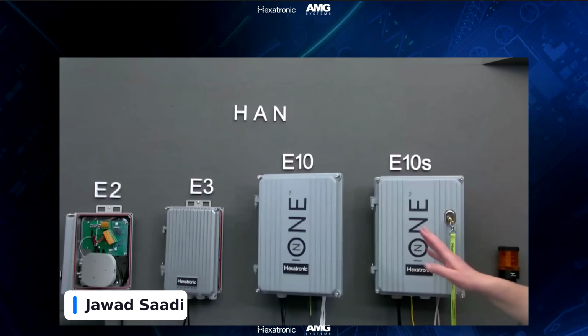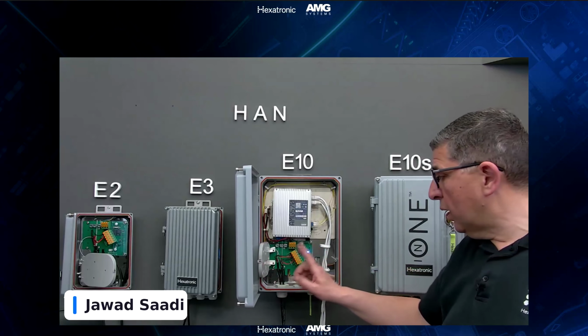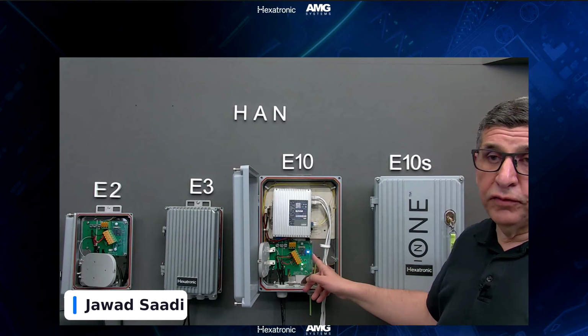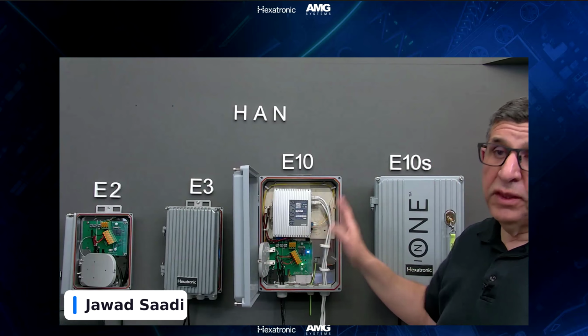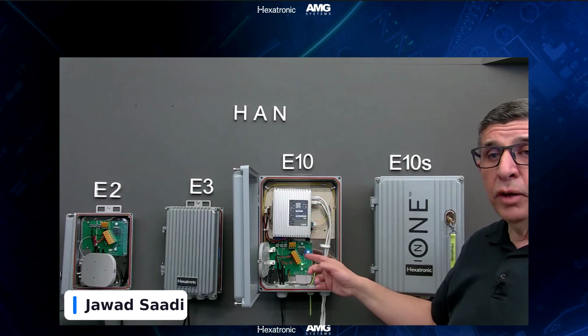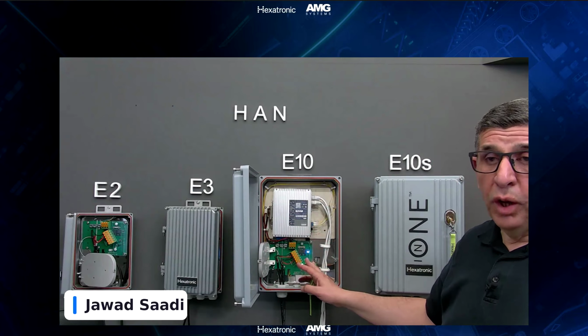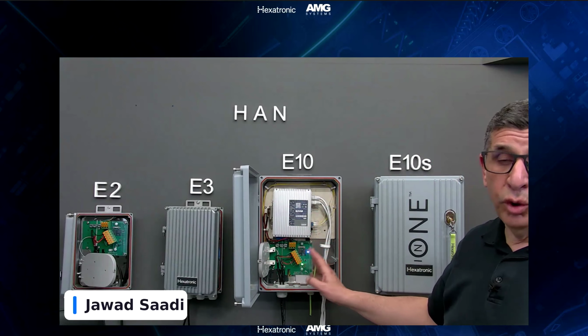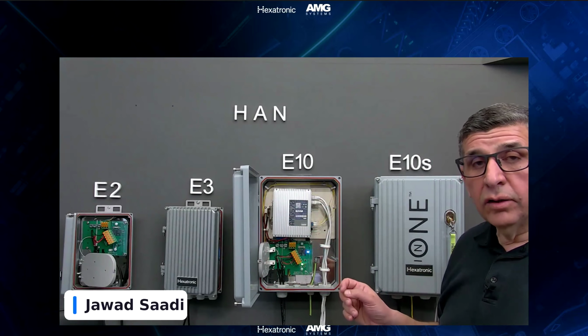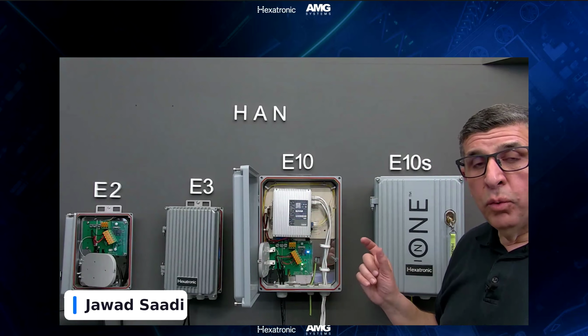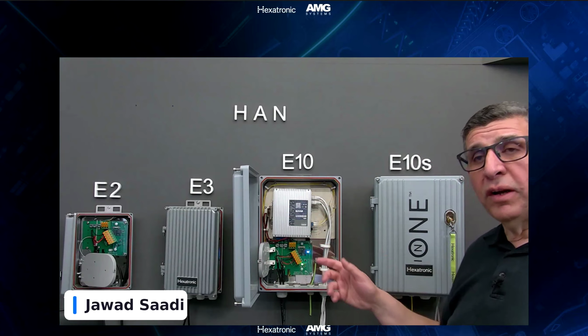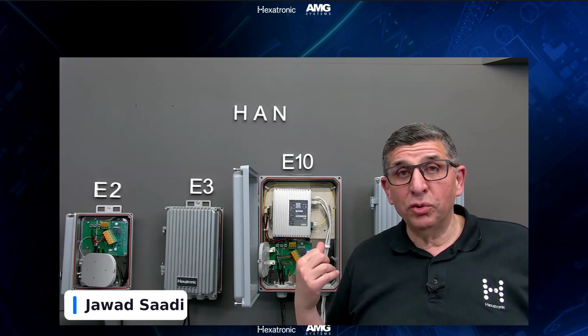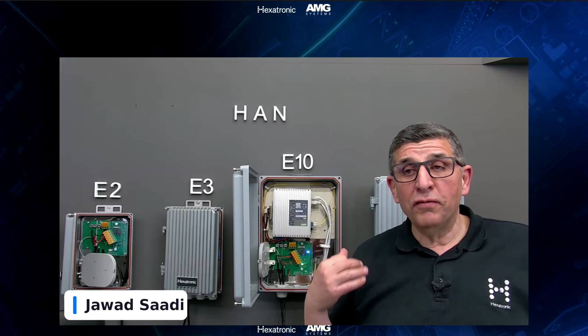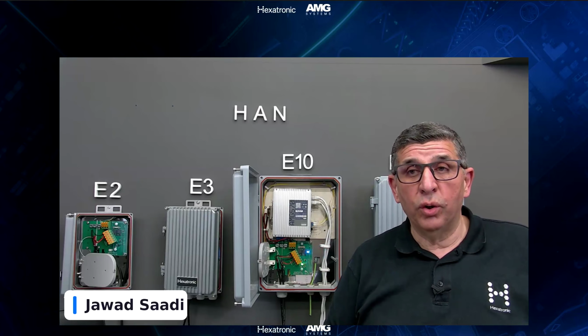Yes. The hybrid access nodes come with two different power cards. This specific power card can deliver 150 watts locally for this box, and then the next box gets another 150 watts. The other model is the high power one, which can deliver up to 300 watts, plenty of power for a single access point. That card can also deliver another 30 watts at 24 volts if you need to connect PLCs. Some of our customers, especially in perimeter security, put a gate controller connected to the box, and then they need 24 volts, or if you want to collect alarms with a PLC, which typically works on 24 volts.